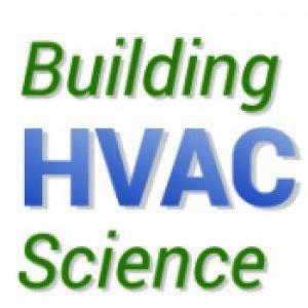But sometimes just finding the information can take you hours to get it for a particular manufacturer. But once you have the information, it's really just interpolation. You've got 4 or 5 things that the tables don't line up exactly. Like they'll have an outdoor design temperature for 95 and 100, and yours is 98. So you have to interpolate between those two. And they'll have a row for 1,000 CFM and 1,200 CFM, and you're at 1160. And so you have to interpolate for that. And it's not that hard to do.